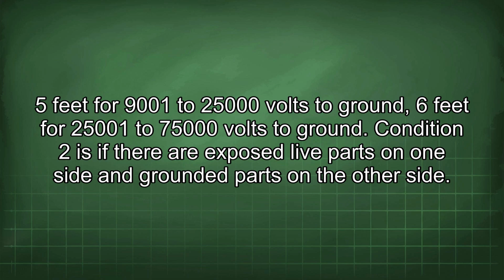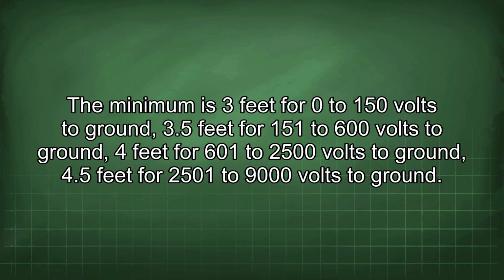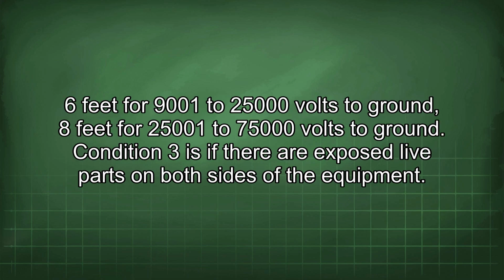Condition 2 is if there are exposed live parts on one side and grounded parts on the other side. The minimum is 3 feet for 0 to 150 volts to ground, 3.5 feet for 151 to 600 volts to ground, 4 feet for 601 to 2500 volts to ground, 4.5 feet for 2501 to 9000 volts to ground, 6 feet for 9001 to 25,000 volts to ground, 8 feet for 25,001 to 75,000 volts to ground.